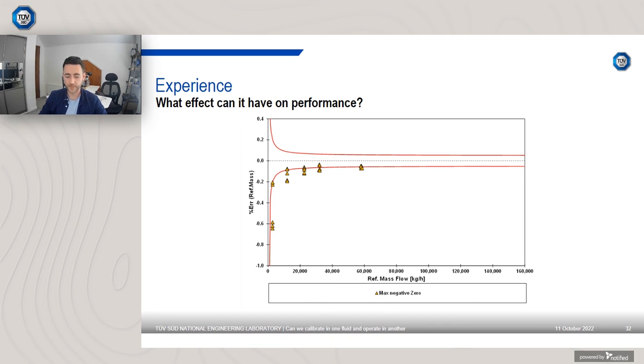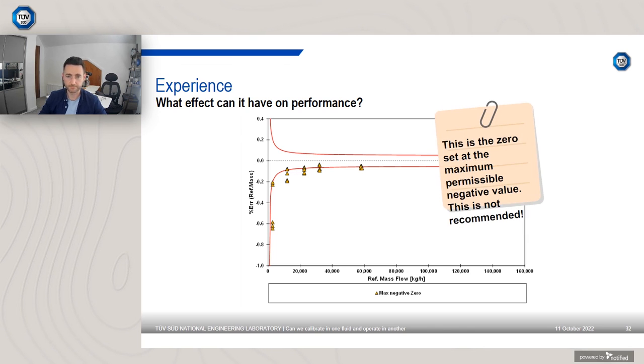Ultimately, if you calibrate the meter in a laboratory and then calibrate it, or check and then calibrate it in your installation, the zero will differ, and as such, those different zeros I was showing you clearly affect the performance of the meter down at this flow range, and that means that the results could be completely different. So you're expecting this kind of performance, for example, and then when you install it, you have a different zero, the results could be sitting up here. So that's why you should certainly be aware of using a Coriolis meter calibrated in liquid and then trying to use it in gas with a completely different zero. Ultimately, it's certainly challenging and maybe not always recommended.